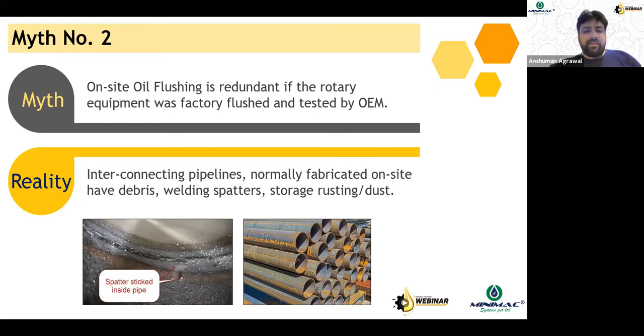And this debris keeps on sitting there till the time you start your system or commission your system. And if you do not perform flushing timely, then this debris actually starts coming off when you start your system and you actually commission it. So there are multiple sites where we have seen that flushing was bypassed, just because flushing was already performed by the OEM earlier.